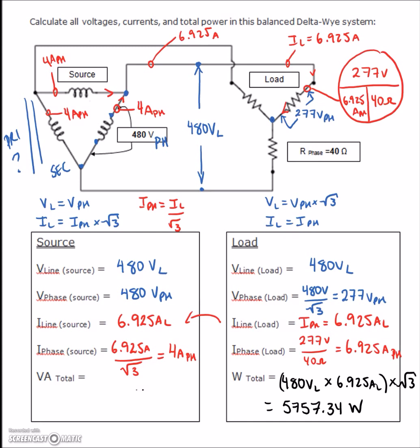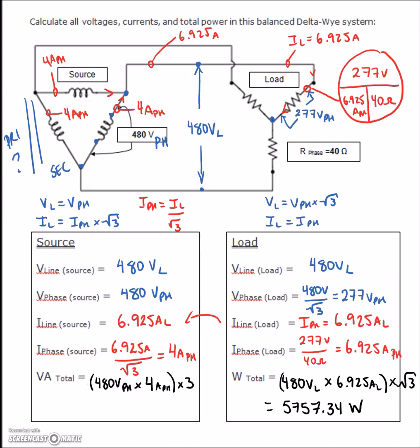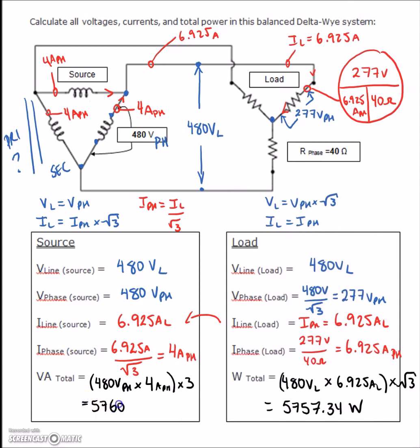We double-check using phase values: V_phase × I_phase × 3 phases = 480V × 4A × 3 = 5,760VA. These values are essentially the same — the small difference is due to rounding errors throughout. We use VA because this is the secondary of the transformer, but it's effectively watts since we have a purely resistive three-phase load.